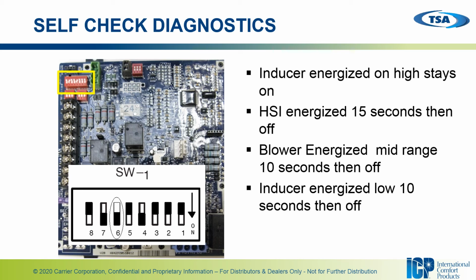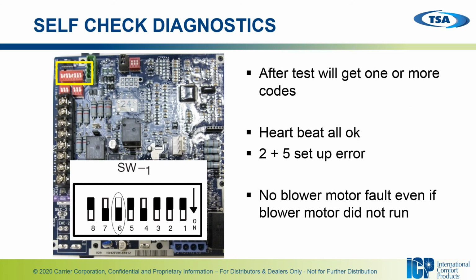Then the blower is going to energize mid-range, typically right around 50% for 10 seconds, then off, and then the inducer will drop down to being energized in the low speed for 10 seconds and then off. Being that this is a two-stage furnace, it's going to check both speeds on that inducer. Once the test is complete, you'll get some sort of code. A heartbeat indicates everything is okay. 2 plus 5 gives you a setup error. It's not going to give you a blower motor fault even if the blower motor did not run, because there is no feedback from the motor.